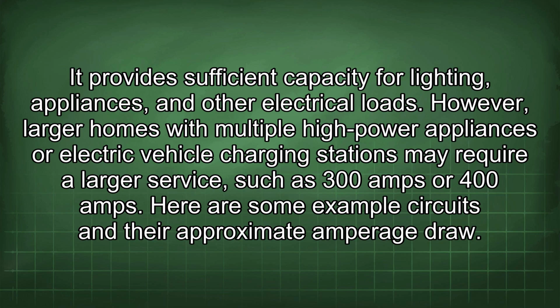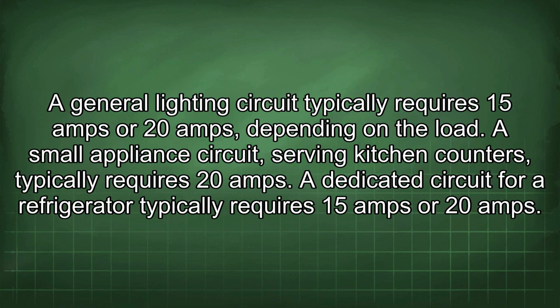However, larger homes with multiple high-power appliances or electric vehicle charging stations may require a larger service, such as 300 amps or 400 amps. Here are some example circuits and their approximate amperage draw. A general lighting circuit typically requires 15 amps or 20 amps, depending on the load. A small appliance circuit, serving kitchen counters, typically requires 20 amps. A dedicated circuit for a refrigerator typically requires 15 amps or 20 amps.